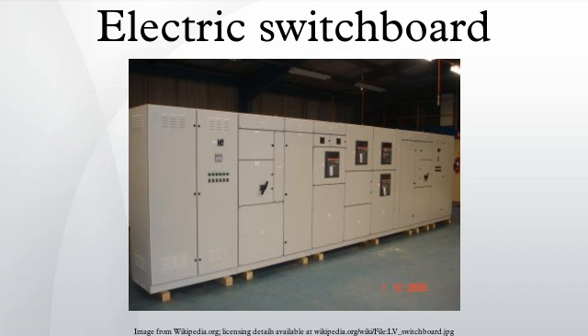Large switchboards may be freestanding floor-mounted enclosures with provision for incoming connections at either the top or bottom of the enclosure. A switchboard may have incoming bus bars or bus duct for the source connection, and also for large circuits fed from the board. A switchboard may include a metering or control compartment separated from the power distribution conductors.